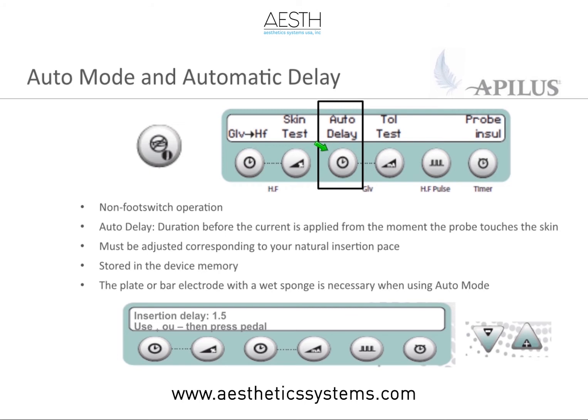So you've already set your settings, your pulses, everything you want for the hair removal. What you need to think about in this screen is how long you need for an insertion. The factory preset comes at 1.5 seconds. If you're working on an area where insertion is easy, you can speed it up, or if it takes longer, you can slow it down.